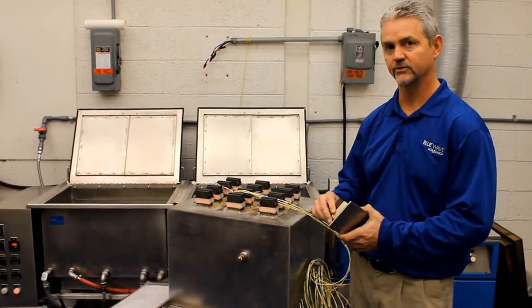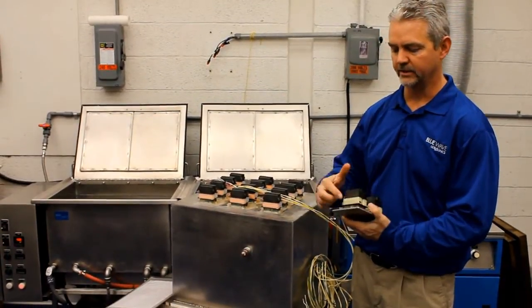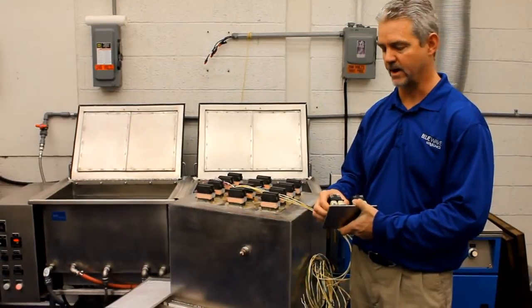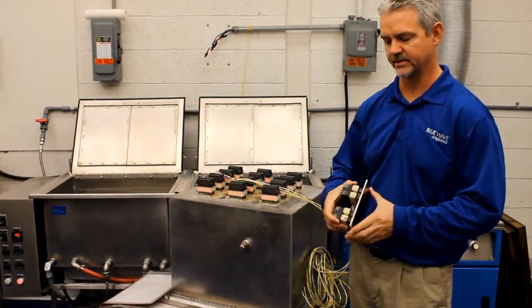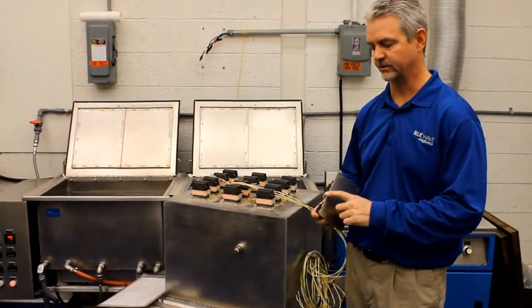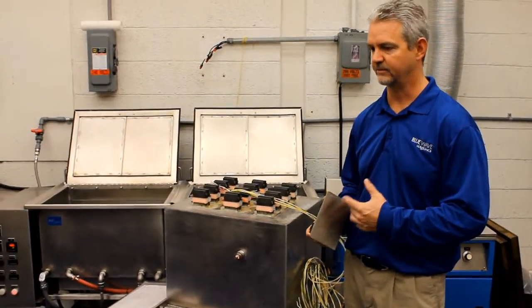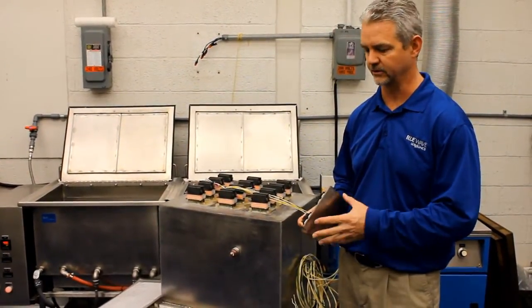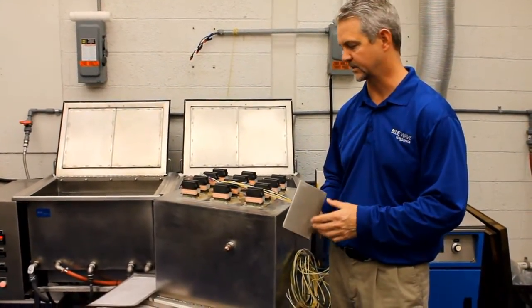We guarantee that the transducers will never lose their ability to expand and contract. We guarantee the silver-braze that there will never be dis-bondment, and we guarantee that you will never pit through this thick radiating diaphragm, provided the chemistry that you're using is compatible with 316L stainless. It doesn't have to be our chemistry. It can be chemistry that you prefer to use, but it has to be compatible with 316L.